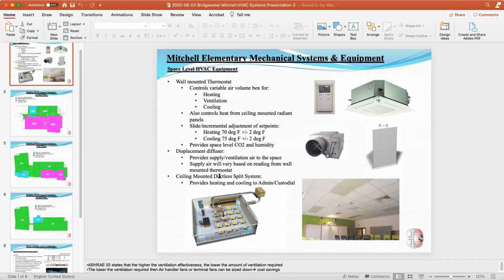Just the CO2 demand ventilation, which is an energy saving strategy, they still allow that, and that's in their recommendations as well. They just lowered the CO2 ppm, which was in accordance with our original design. So, long answer, the short one would be, I think the design is well suited and in line with the ASHRAE recommendations for airflow. It certainly also would recommend, before occupancy, the building purge, where we run it all in outdoor air mode for a number of weeks to clear out any harmful VOCs, which is pretty standard nowadays.